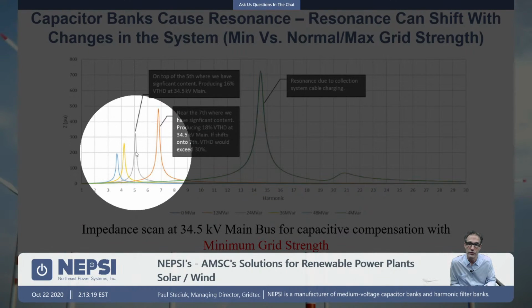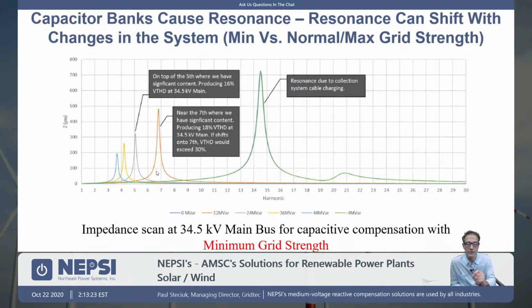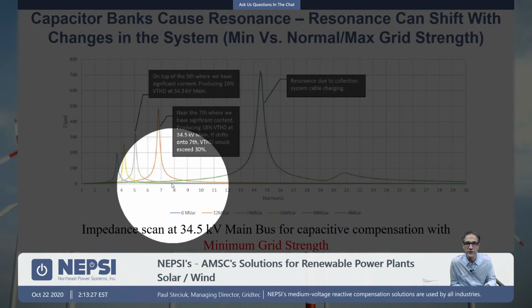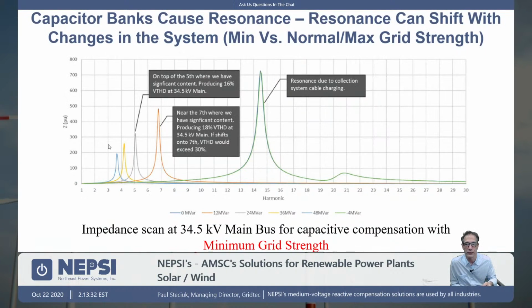As we kick stages on, you can see here our resonant point moves around. And here you can see we're kind of over the 5th harmonic. Here we're close to the 7th. And even with some shifts in the short circuit impedance, the grid strength, as we noted here, we're going to have these possible resonances. And these are concerns that the developer will run into.